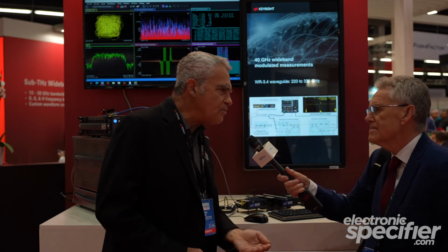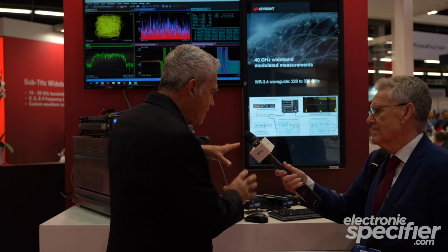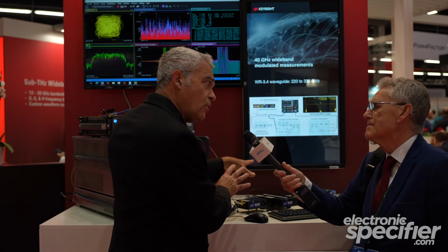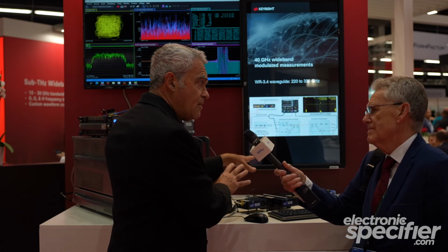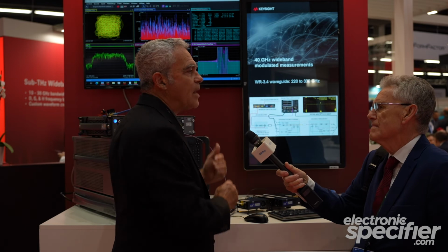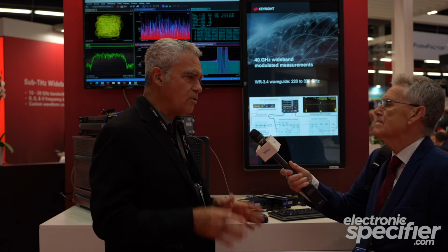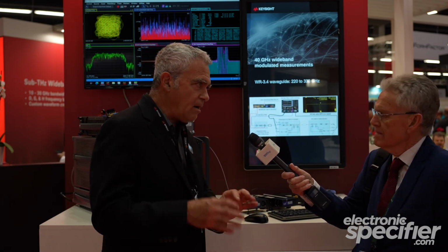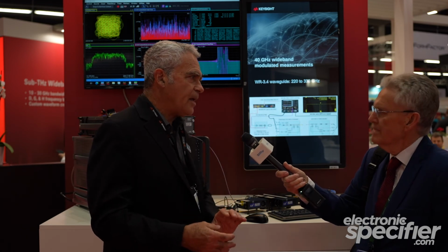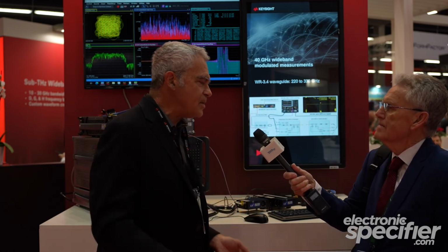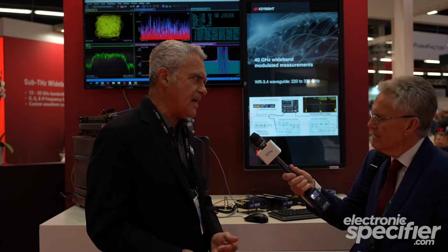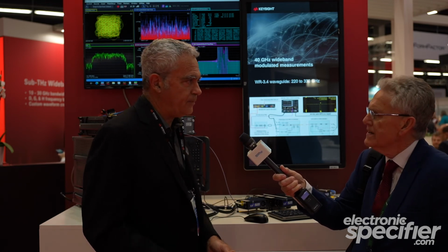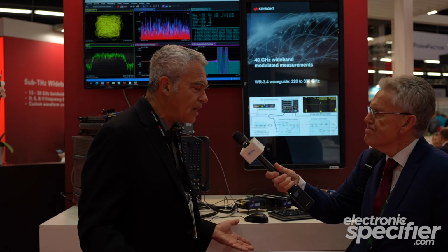But before that, we do a legacy S parameter. So this system still has the capability to do legacy S parameter using the same calibration. Then we go to wideband signals. So you can start with your DUT in S parameter mode, look at the gain, look at the frequency response, and then, okay, now it's time to apply a wideband modulated signal to this device and see what's going on, without disconnecting, keeping the same calibration.